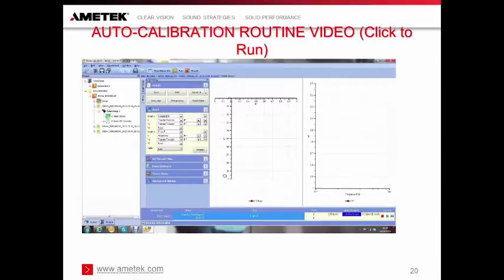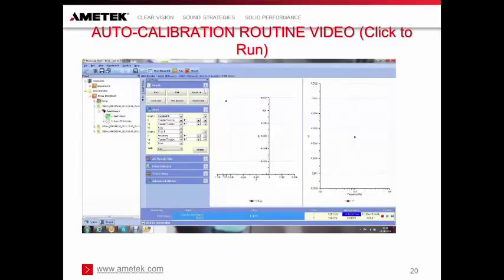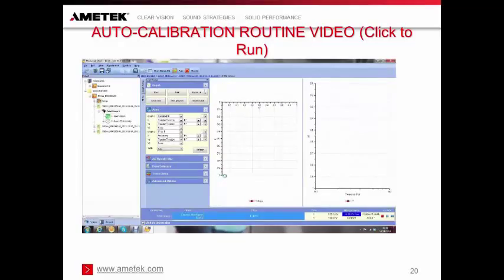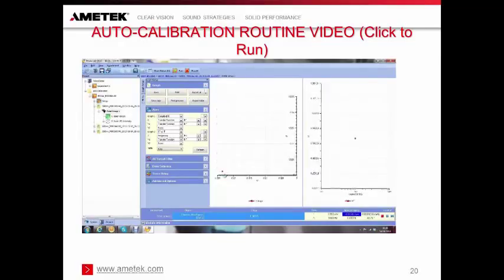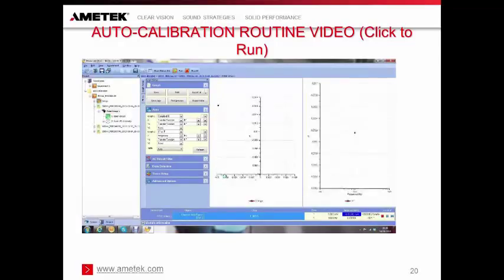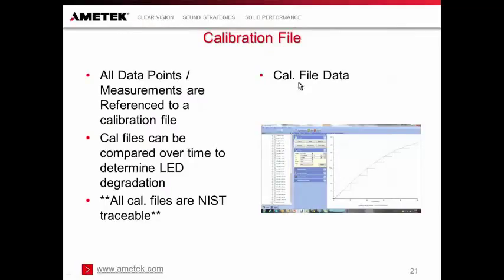There are two methods of calibration. We have to calibrate for software control and calibrate for hardware control. But as far as the customer is concerned, this doesn't matter. This is all fully automated. So now we're performing the calibration, and it's going to store a calibration file. So once we've finished that experiment, which is about 2 minutes in duration, this is a typical calibration file.